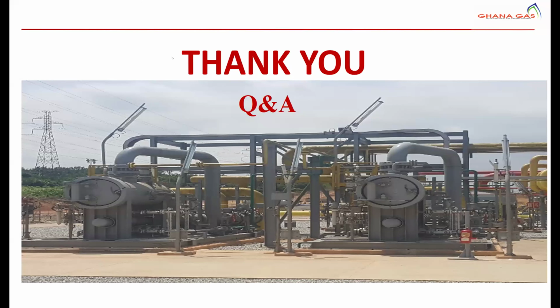We calibrate the gas chromatographs, and not only the gas chromatographs, but almost every piece of equipment we have in-house, even our PSVs, pressure safety valves. Our weighbridge, for instance, that we use to weigh the condensate that we sell to the market, is also calibrated. Calibration is very key for us. We engage the standards authorities for the ones that need an external party, but for the ones that have to be done internally, we have the expertise in-house. So that is it.